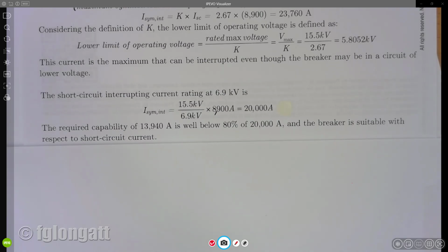Of course, I know that people coming from consultancy work or from utilities will tell me, okay, this is very academic, but in real life there are many other ways to do this. And I will agree with you in some very specific cases. If you know the manufacturer of the circuit breaker, they provide documentation that can be used, and you can get another method to calculate things. But in this case, I want my students to have a taste of and understand the basic procedure, and understand the relationship between short circuit levels and specifying these kinds of circuit breakers.